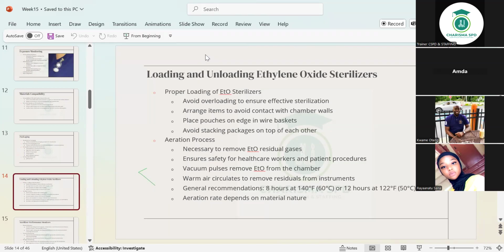If it's not like that, just make sure your instruments are not touching the walls in the autoclave, okay? So place pouches on edge in wire baskets. The pouches are the envelope type that I told you. They should be on edge, like you're putting books on a bookshelf in the library. They should be on the edge like that. So the plastic side should face the paper side of the next pouch. Okay? Is that understood?